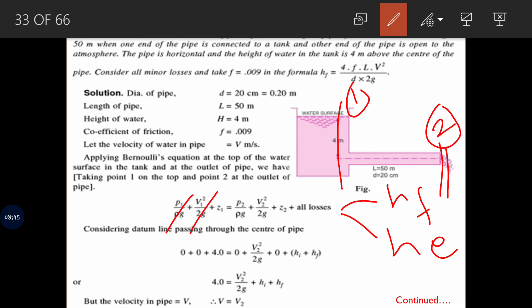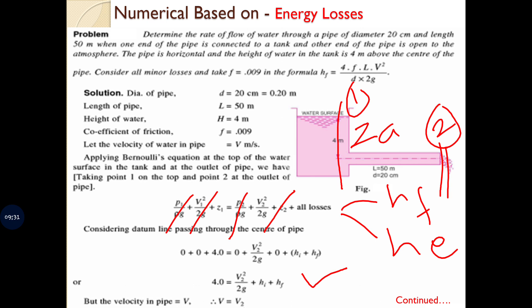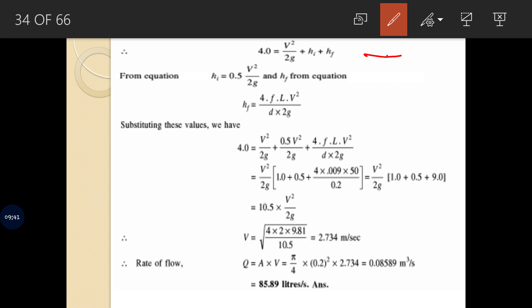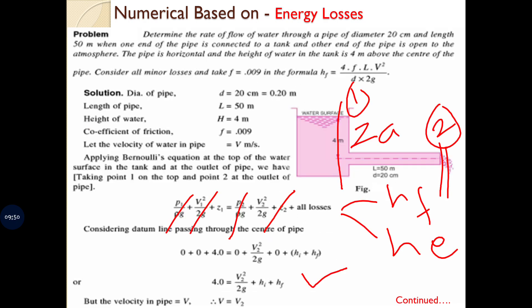z1 is the datum head; the height from the centerline is 4 meters, so z1 = 4 m. z2 is zero as the centerline itself is the datum. The simplified equation becomes: 4 = V2²/2g + all losses. V2 is replaced by V (velocity in the pipe). Major loss is due to friction and minor loss is due to entry into the pipe.